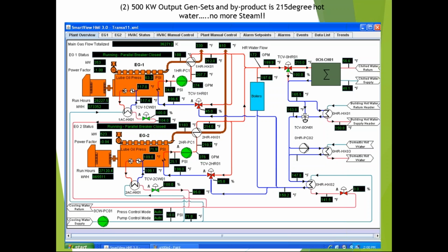But my engine's delta rise is 20 to 22 degrees, and that's it, right? So what happens is that there's a TCV valve, a three-way valve, where jacket water coming out of the engines, all that energy I put to make that warm, make it hot, now I got to send it right back in short cycle. So I got to mix my 150 and make it 196. That's my target going into my engine block. So then at the very end of it, through everything, I'm getting 210, 215.